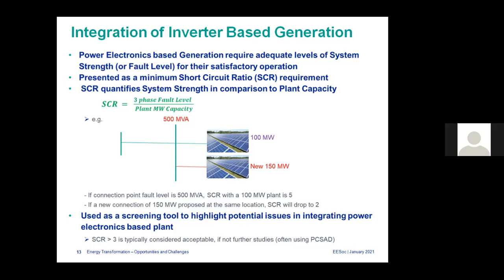In this example, if you have a 100 megawatt plant, we have an SCR of 5. But if you add another 150 megawatt plant, the SCR will drop to 2 because we now have 250 megawatts. The fault level remains the same because these are asynchronous generation, so the fault level contribution is negligible. So normally you use the synchronous fault level, which is still 500, divided by 250, and you end up with about 2 as the SCR.